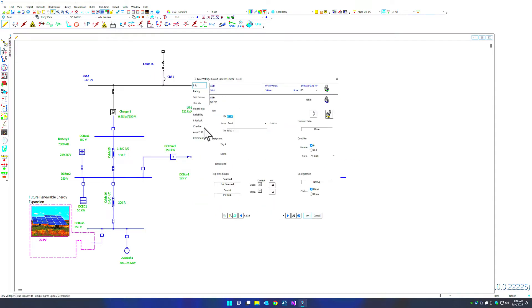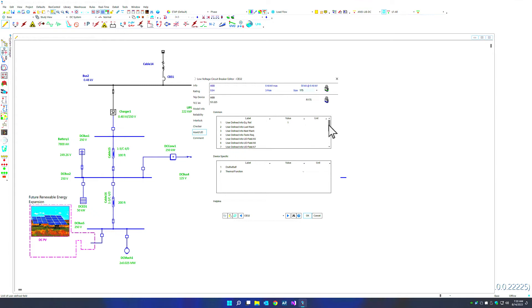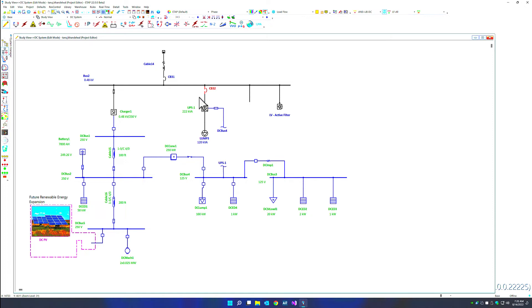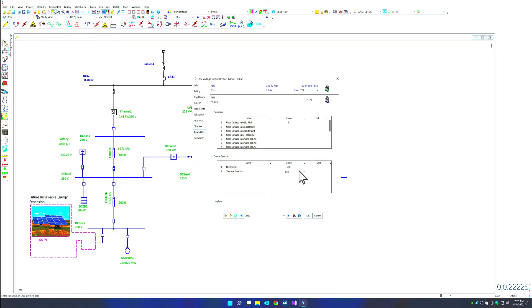We can open up our low-voltage circuit breaker, go to the asset or user-defined fields, and see our 'last maintenance date' date-type field as well as our device-specific fields. In the numeric field, if you type in 900, it will reset to the maximum value of 500. The thermal function can be yes or no — since we only included yes, a blank implies no, and you can easily select yes. All this data is saved with the component using its common and device-specific user-defined fields.